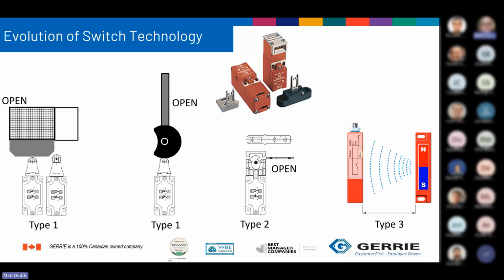Type 2 for a lot of customers became the standard. However, they are not without their issues. Increased wear of plastics due to poor alignment of the actuator led to metal guides being installed or created, and then adjustable keys to aid with self-alignment on short radius doors, and then even double adjustable keys to give a full movement of actuation. So again, these were designed for short radius doors. They actually weren't designed for misalignment. The key should be aligned when it goes into the switch.